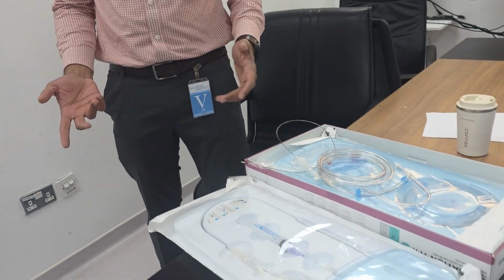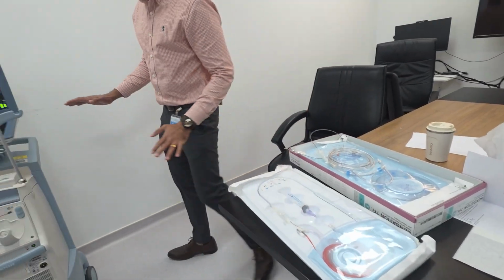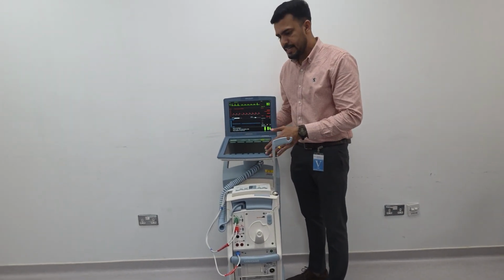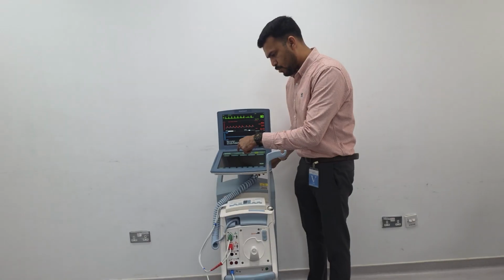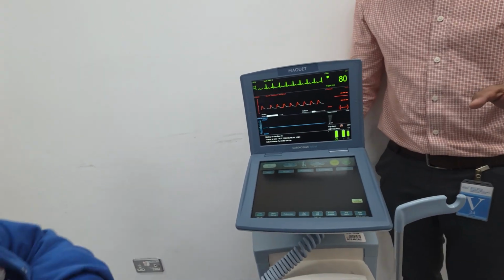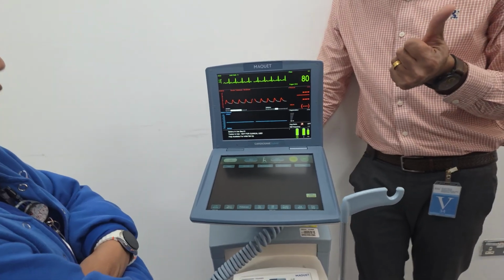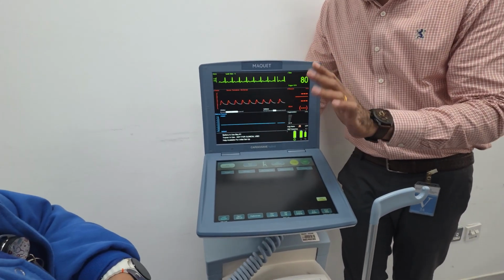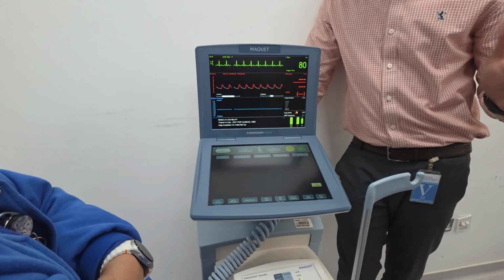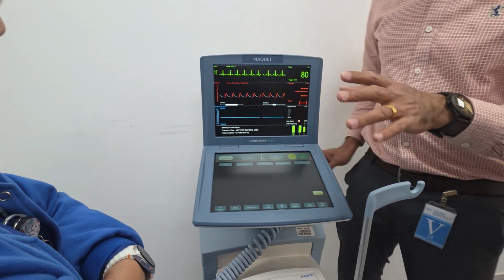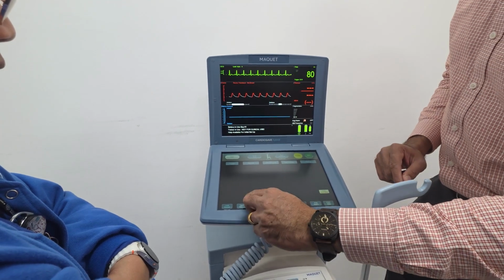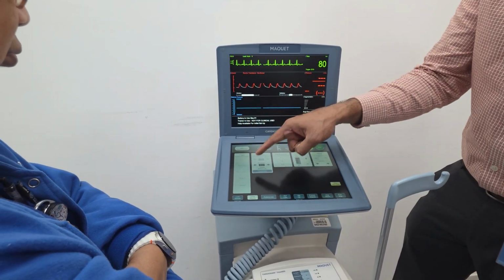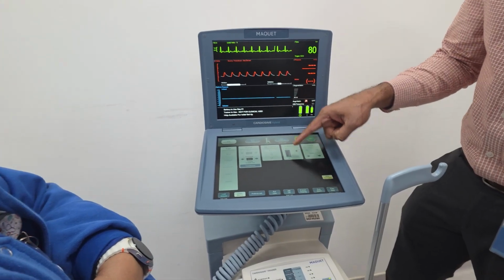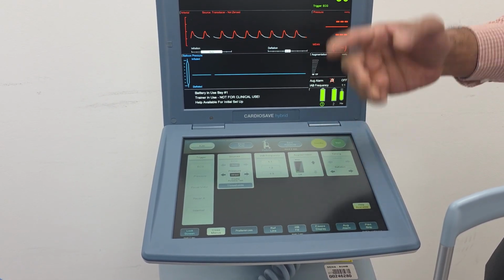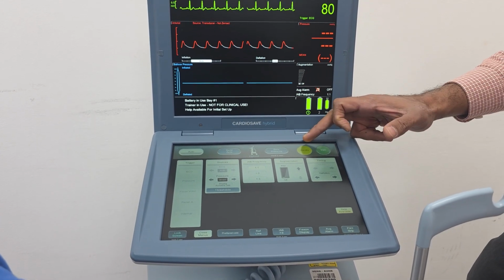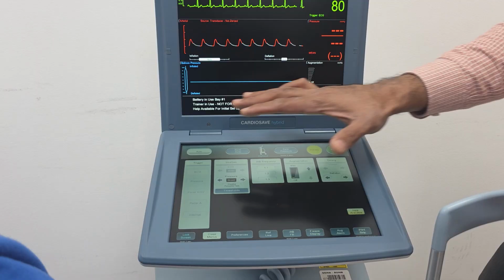Since you are using the CS300, you can start it here. The only difference is it has a touch screen, but the design is almost similar. Okay, you can see two modes of operation, but there is no manual mode because we are not providing any manual mode for pediatrics. There is no pediatric balloon, so auto and semi-auto only. The functions and keypad are the same as the CS300, only aligned in a different way. Okay, so we can open the menus. You can see all the menus here. See, the same way: trigger, sources, frequency here, augmentation, and the timing. Some additional features seem to be here. That's it basically. And standby and start is here. Same design, only it's a touch screen.